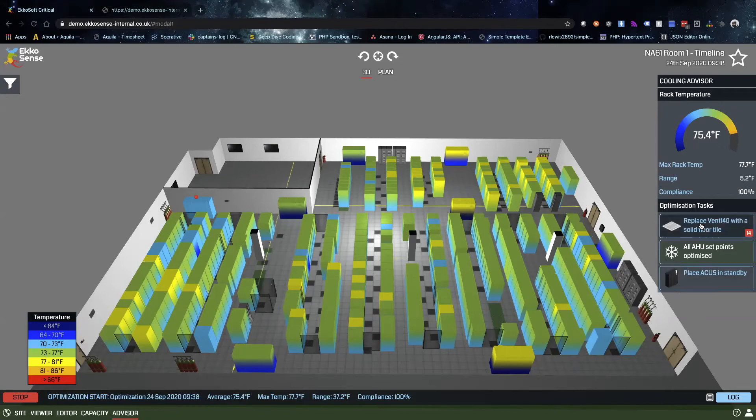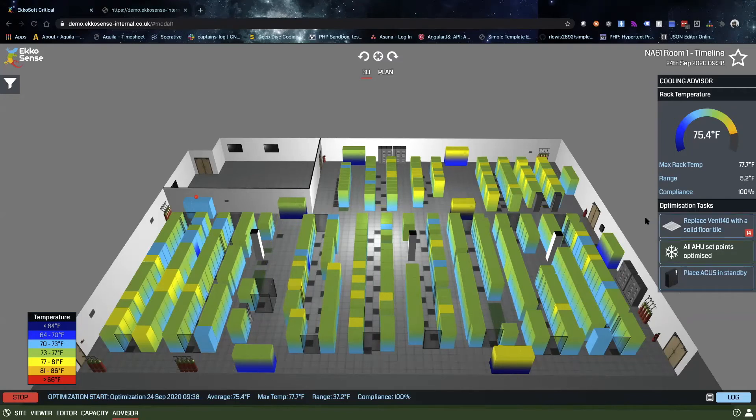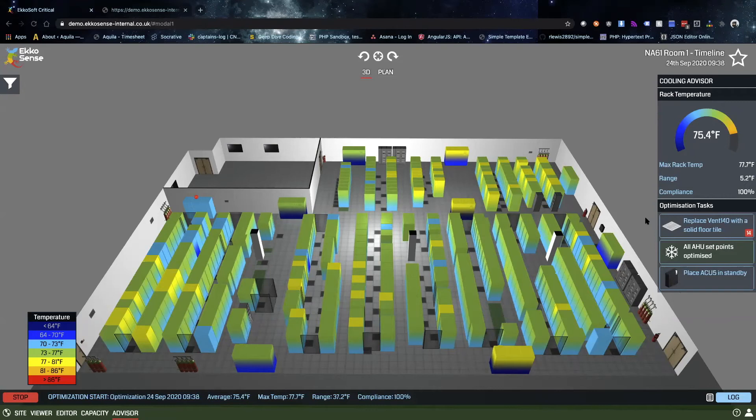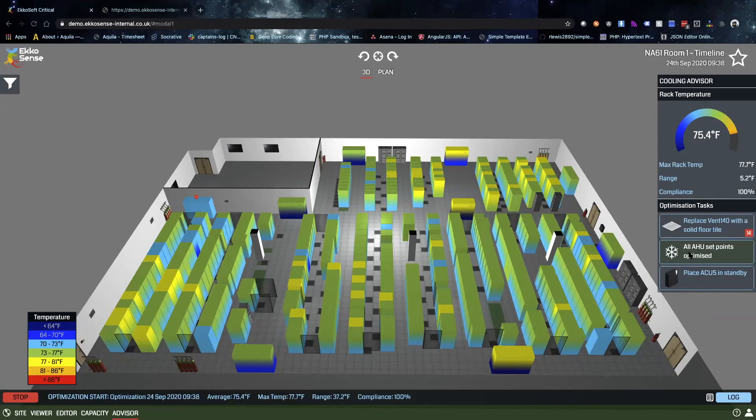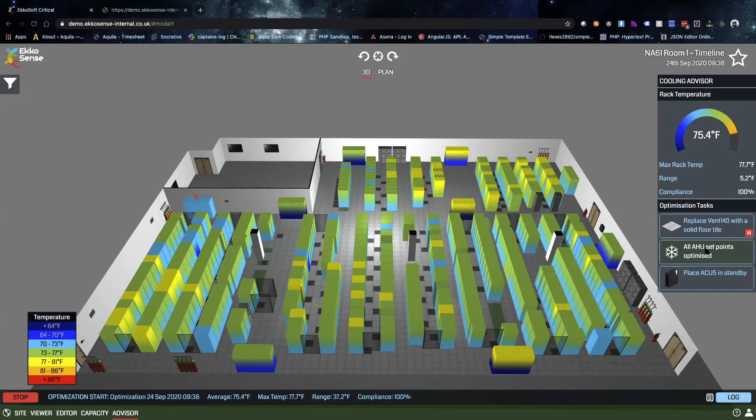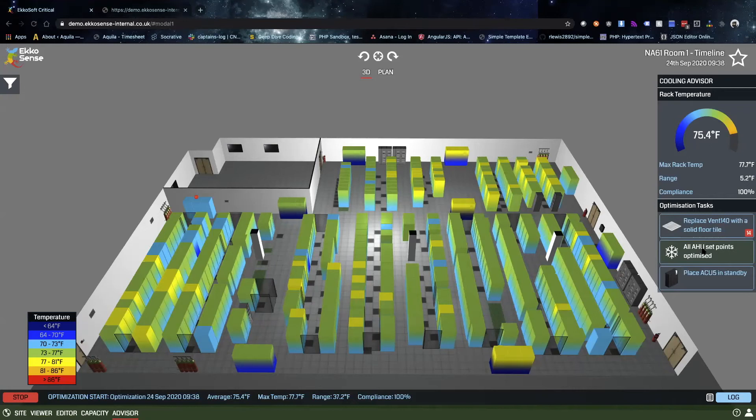Recommendations come in three forms: the location of supply tiles, so the software is considering every tile in the room and whether it should be a solid tile or a supply tile. It's also looking at the set points of the cooling units and comparing that along with the zones of influence and the intake temperatures to the cabinets. Cooling units could potentially have their set points adjusted, most likely increased but they may actually need to be decreased in some cases to make sure that the primary goal of the cooling infrastructure is to provide the appropriate intake air temperature to IT equipment.